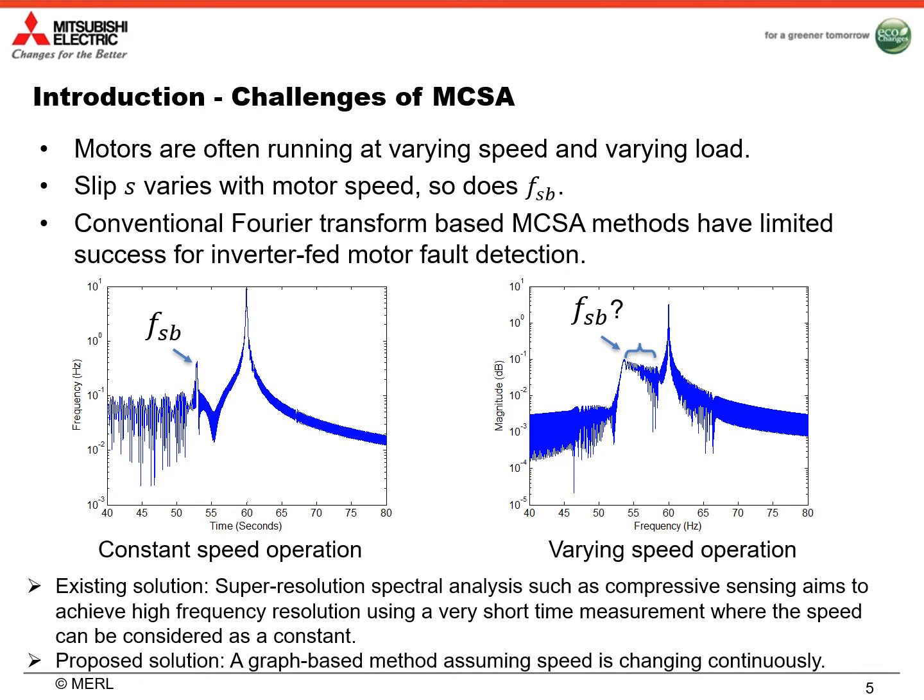To solve this problem, super-resolution spectral analysis such as compressed sensing aims to achieve high frequency resolution using a very short time measurement, where the speed can be considered as a constant. However, this method may suffer from noisy measurements. In this paper, we proposed a graph-based method which assumes the speed is changing continuously. Using our proposed method, we can still effectively extract the fault signature even under varying speed operation.